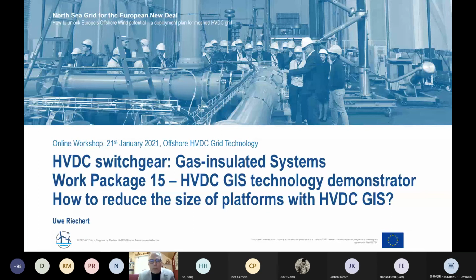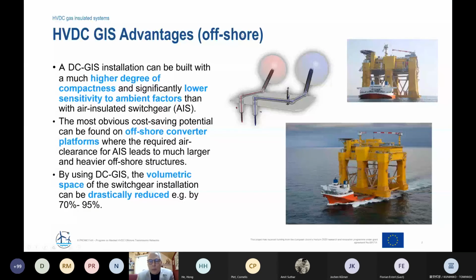And now I will pick up one of the topics you mentioned and focus on HVDC gas-insulated switchgear. If you compare an AC gas-insulated switchgear with a DC gas-insulated switchgear, then you will see that an HVDC GIS installation can be built with a much higher degree of compactness and a significantly lower sensitivity to ambient factors. That is known from the AC side, and that is the same also for DC. Based on that, the most obvious cost-saving potential can be found on offshore converter platforms, where the required air clearance for an air-insulated substation leads to much larger and heavier offshore structures. So summarizing, it can be said that by using an HVDC GIS, the volumetric space of a switchgear installation can be reduced by 70 to 95%, depending on the design of the HVDC platform.